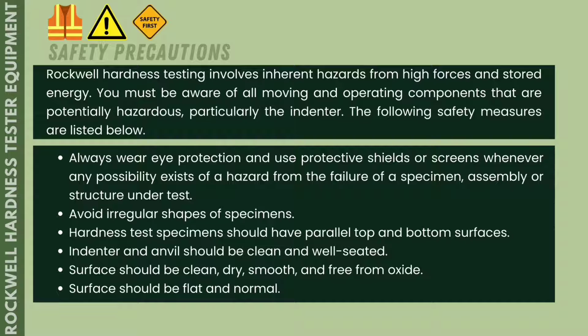Rockwell hardness testing involves inherent hazards from high forces and stored energy. You must be aware of all moving and operating components that are potentially hazardous, particularly the indenter. The following safety measures are listed below. The first one is to always wear eye protection and use protective shields or screens whenever any possibility exists of a hazard from the failure of a specimen, assembly, or structure under test.